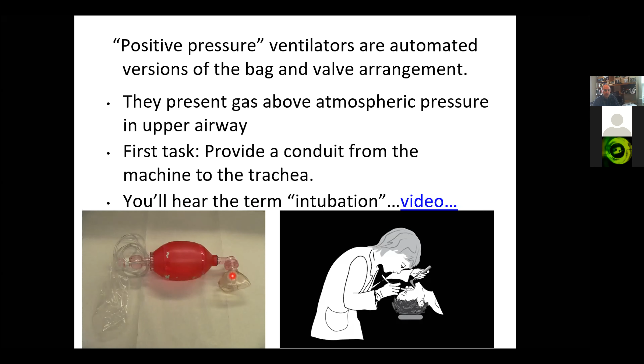So let's take a look at that process. The tube itself, the most common type of these, is a polyvinyl chloride tube. It is large enough diameter not to provide much resistance to airflow, although necessarily it's narrower than the trachea is. It has a tube long enough to go into the trachea and come out the patient's mouth or nose. It has a balloon here, the cuff, that can be inflated by this line to a spring-loaded one-way valve that connects to a standard syringe. It's called a Luer fitting. It has a valve here, so air can be instilled from outside the patient's mouth into the cuff. Now, that cuff is what will provide a ring seal from the inside of the patient's trachea all the way to the inside of the tube.